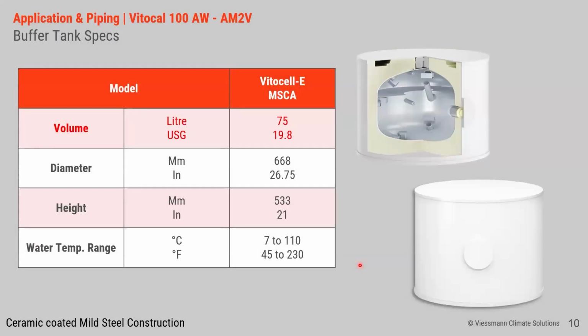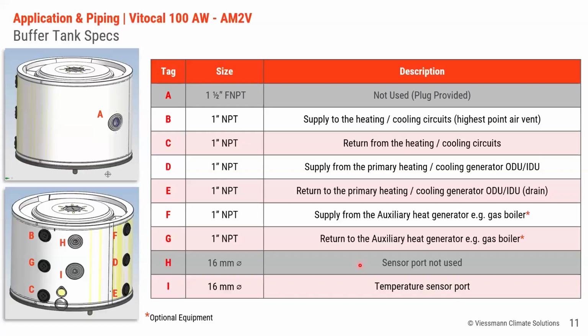Buffer tank is standard with this, so it's a 75 liter or 19.8 gallon buffer tank, and it was designed for this heat pump system. So I know there's been other people saying, well, what can I use a buffer tank that I prefer or whatever? Yeah, certainly you could substitute a different buffer tank as long as it had the specifications of the pressure separation that you need in a buffer tank. But this is what comes with the unit. You're already buying this because it's come stock with the unit. So in most cases, you're going to use the buffer tank we supply. Now, as far as the connections on that, again, are 1 inch. Everything is 1 inch all the way through the board here. There's two temperature sensor wells, and we're going to show you how we're going to look at one of those sensor wells for a possible application.